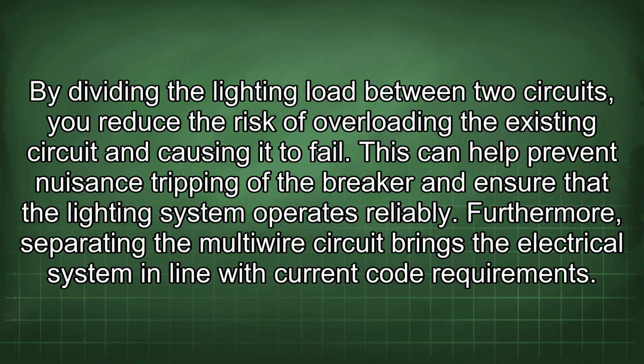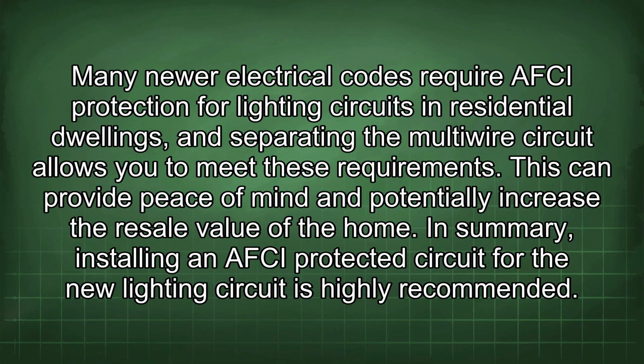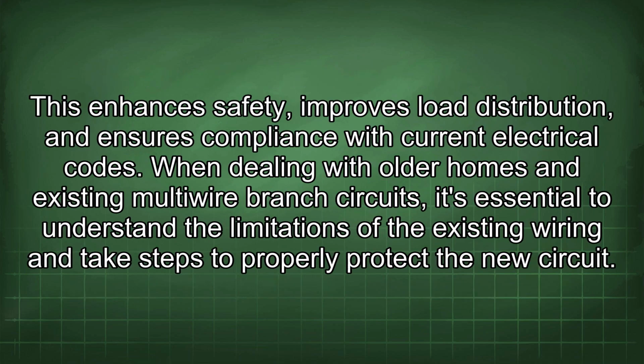Furthermore, separating the multi-wire circuit brings the electrical system in line with current code requirements. Many newer electrical codes require AFCI protection for lighting circuits in residential dwellings, and separating the multi-wire circuit allows you to meet these requirements. This can provide peace of mind and potentially increase the resale value of the home. In summary, installing an AFCI protected circuit for the new lighting circuit is highly recommended. This enhances safety, improves load distribution, and ensures compliance with current electrical codes.